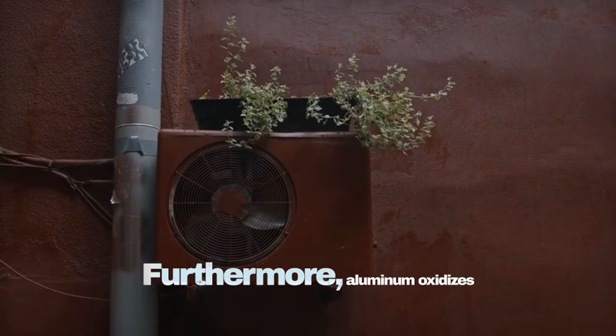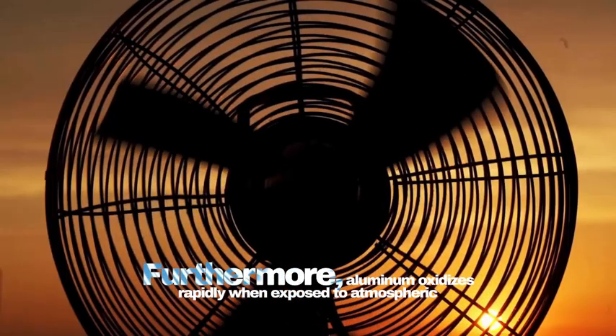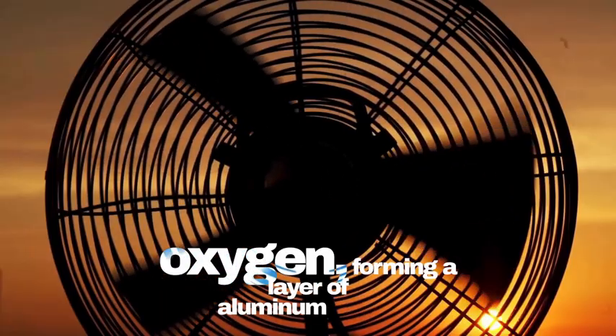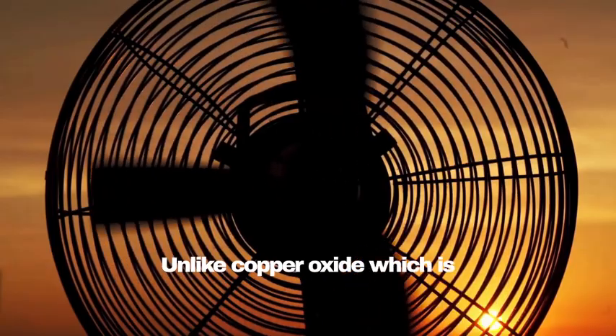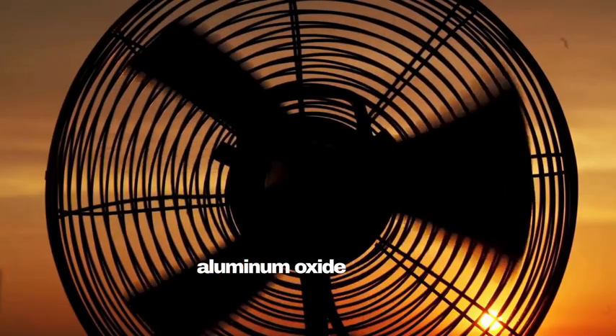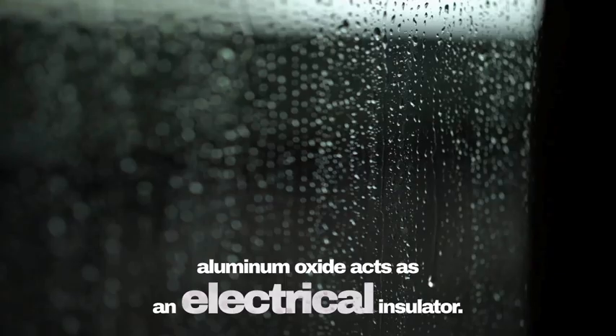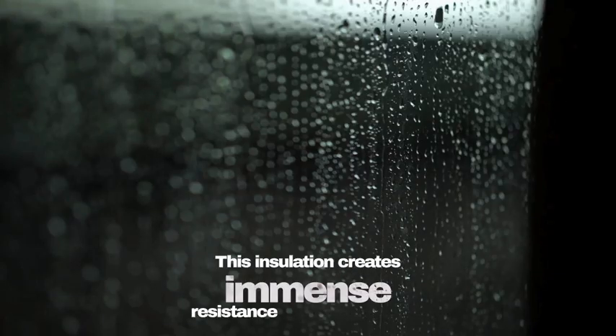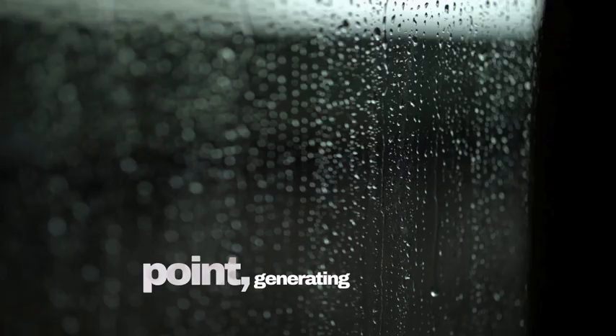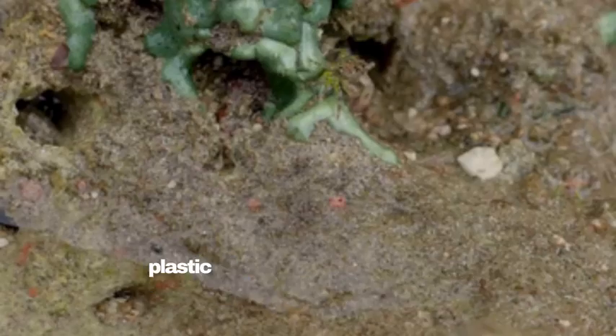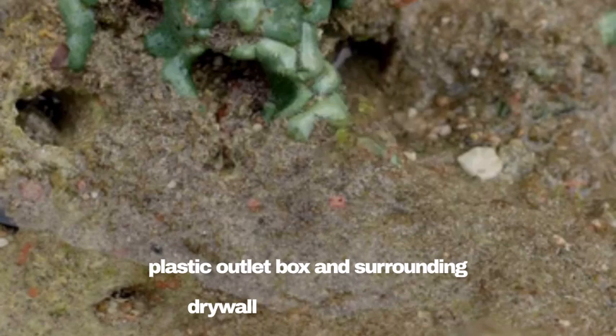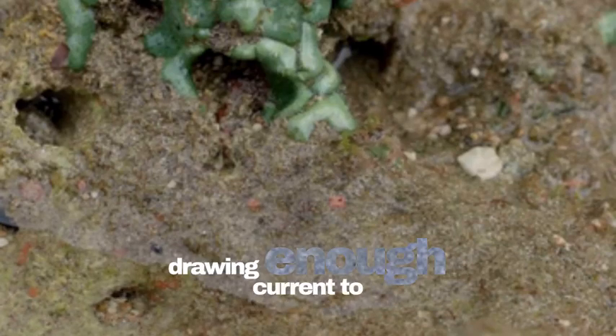Furthermore, aluminum oxidizes rapidly when exposed to atmospheric oxygen, forming a layer of aluminum oxide. Unlike copper oxide, which is highly conductive, aluminum oxide acts as an electrical insulator. This insulation creates immense resistance at the connection point, generating temperatures high enough to ignite the plastic outlet box and surrounding drywall without ever drawing enough current to trip the breaker.